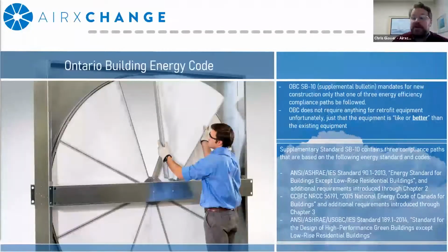Okay, so the Ontario Energy Code actually has 3 different paths for compliance, and they're all for new construction. So, unfortunately, it doesn't look like there's any code-related mandate for existing buildings other than to replace with, quote unquote, like or better. Now, I highlighted better because ERVs can really assist in the better department. The first compliance path is ASHRAE Standard 90.1, which is the energy standard for commercial buildings. The second path is the National Energy Code for Canada. Both use a very similar methodology, or exact methodology, for determining energy recovery. And the third is the Standard 189, which is what I consider the stretch standard, or the high performance standard for commercial buildings.